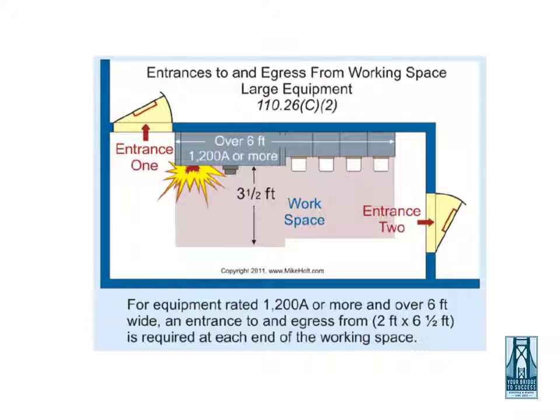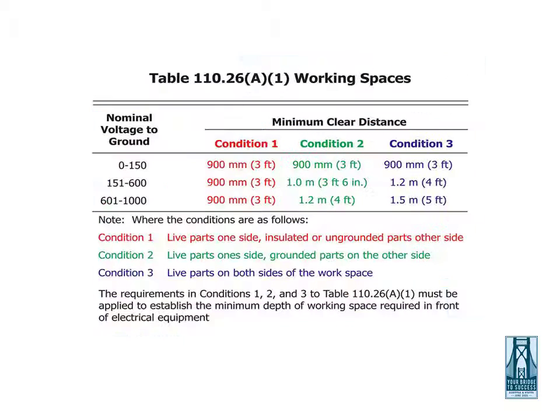With the increase of your service size, other potential code issues arise, such as working clearances, additional sections of switchboard or switchgear for distribution, and the requirement for 2 means of egress on opposite sides of your electrical room. These egress requirements occur when your service is rated 1,200 amps or more and equipment length is over 6 feet in length.